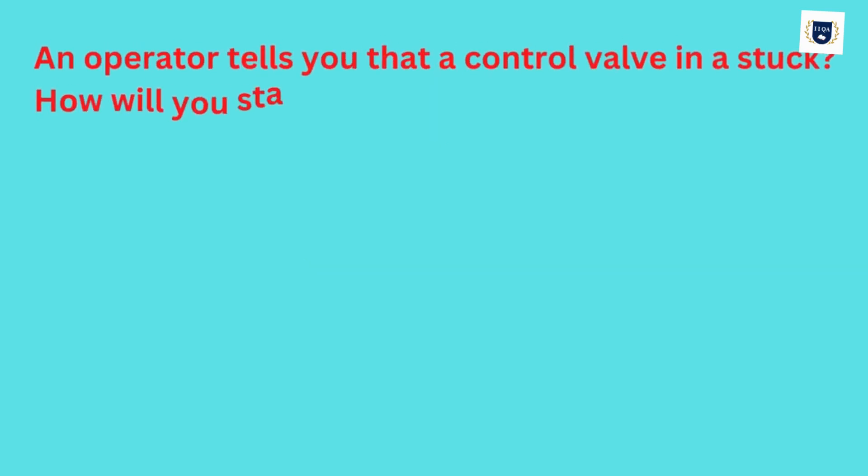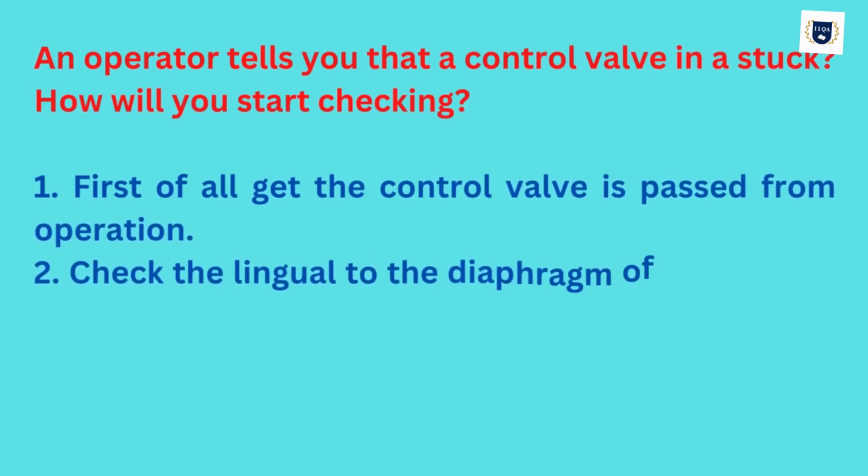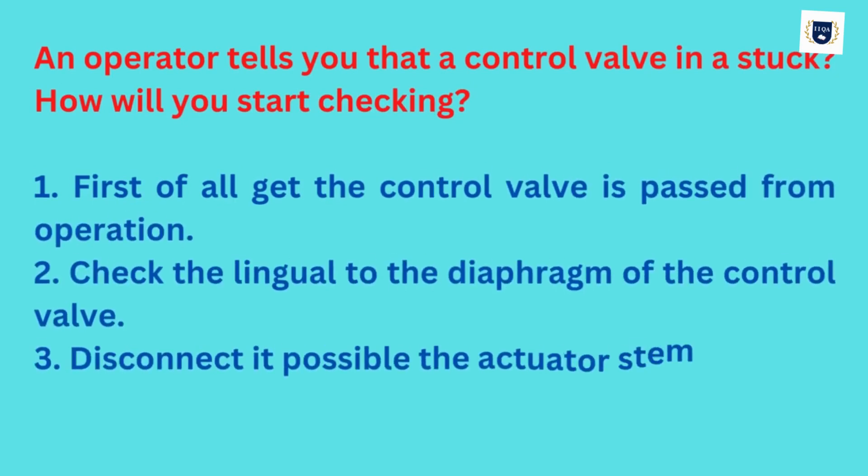An operator tells you that a control valve is stuck. How will you start checking? First of all, get the control valve bypassed from operation. Check the linkage to the diaphragm of the control valve. If possible, disconnect the actuator stem from the control valve stem.